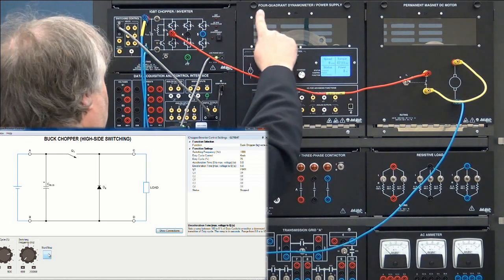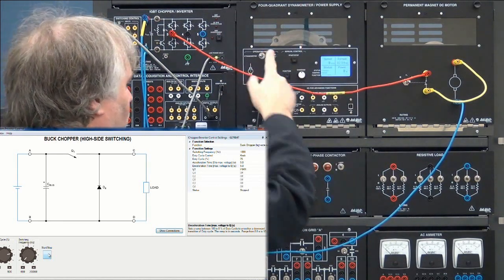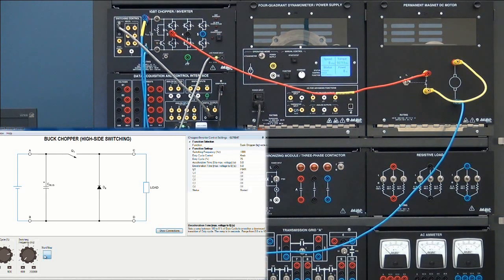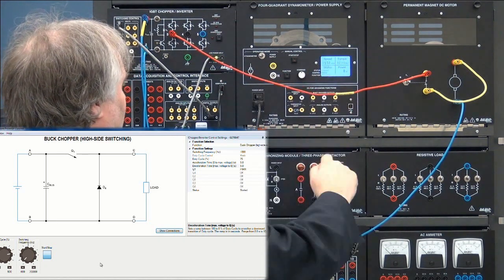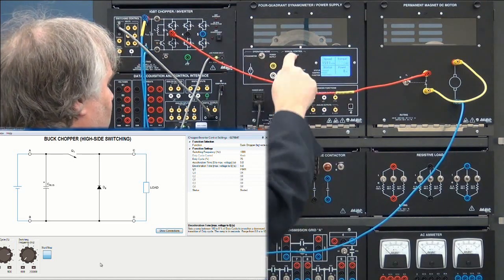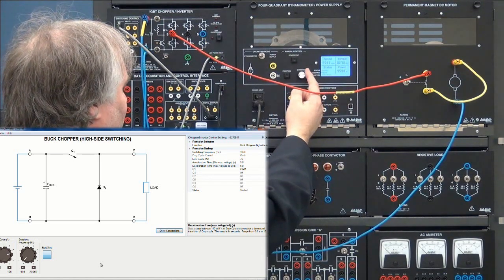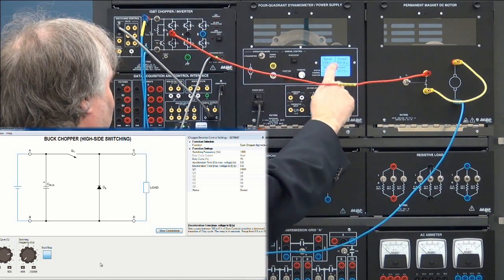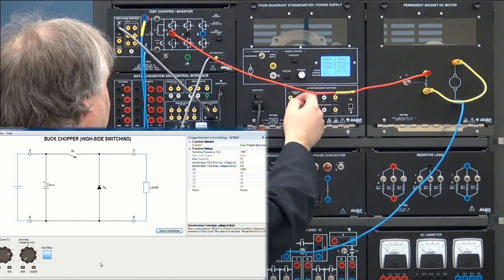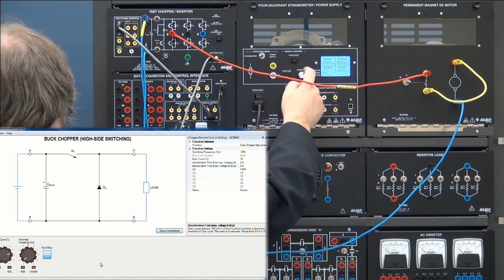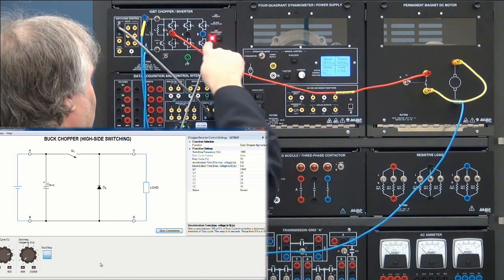So if I put my four quadrant dynamometer into the dynamometer mode, into the brake mode, and I start my function here I will monitor the actual speed. And I can also apply a braking torque. Let's say I start at zero and slowly increase that torque. I can see my mechanical power and I can also see that the torque change and the speed changed. Until a point where if I apply too much torque I should be able to go into over current.